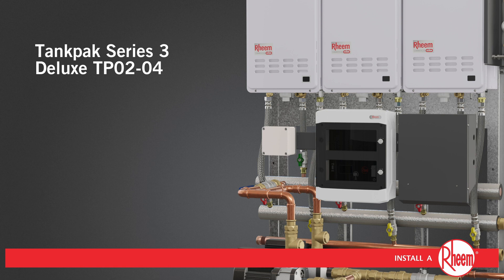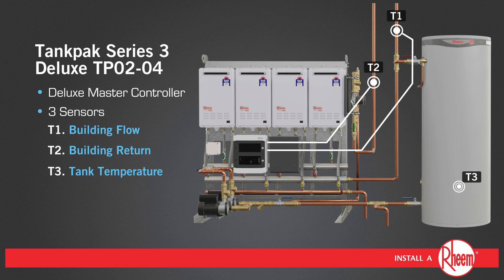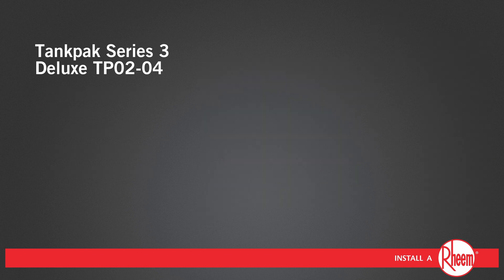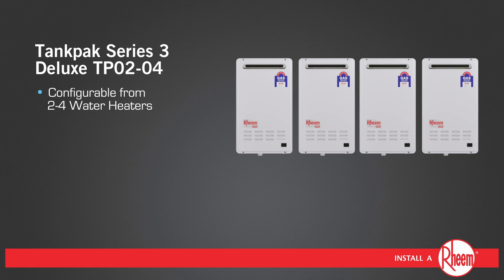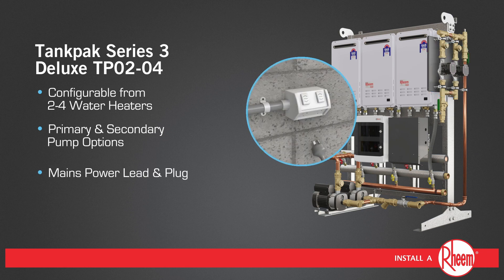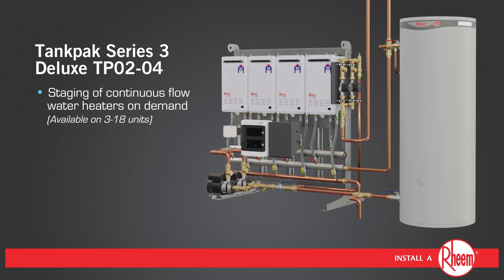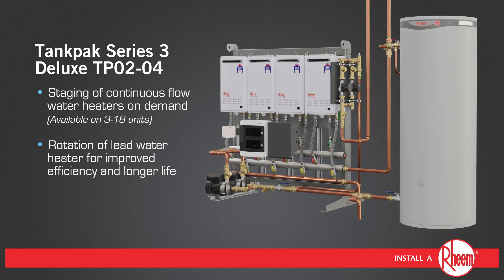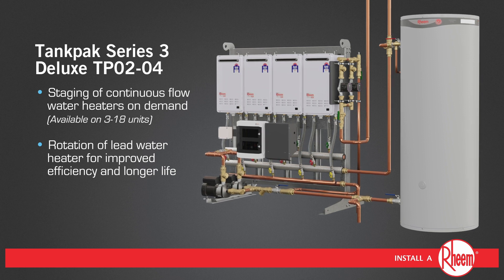Tankpak Series 3 deluxe TP02 through to 04 features a deluxe master controller and three sensors to monitor the building flow, building return and tank temperature. Tankpak Deluxe can be configured with two to four water heaters and is available with up to two primary pumps and up to two secondary pumps on frame, and is supplied with a mains power lead and plug. Tankpak Deluxe features staging of the continuous flow heaters on demand and rotation of the lead water heater for improved efficiency and longer life by minimizing startup of unrequired water heaters.